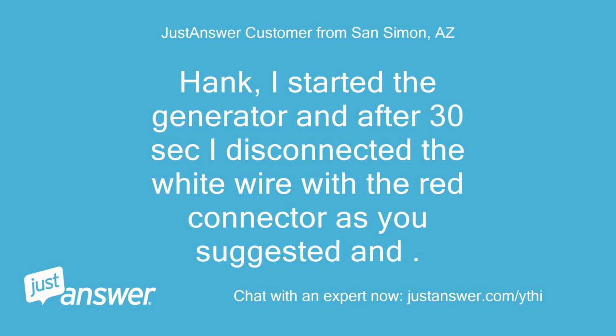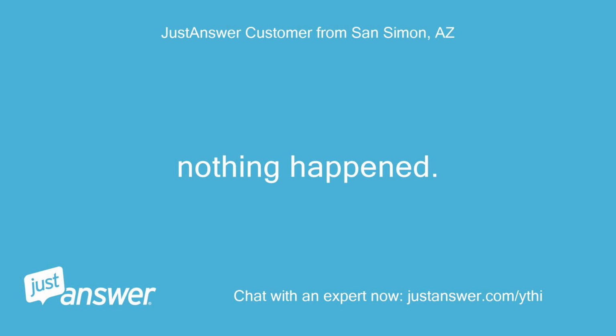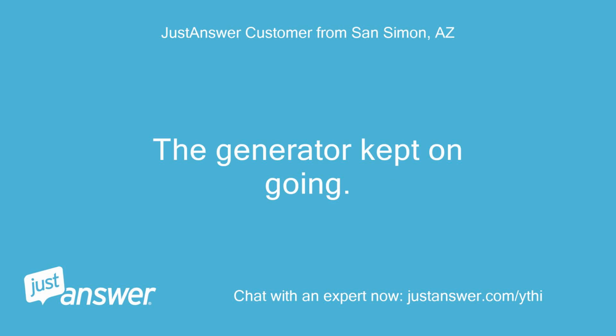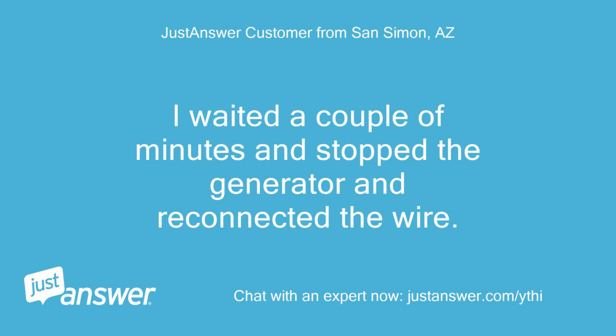Hank, I started the generator and after 30 seconds I disconnected the white wire with the red connector as you suggested and nothing happened. The generator kept on going. I waited a couple of minutes and stopped the generator and reconnected the wire.